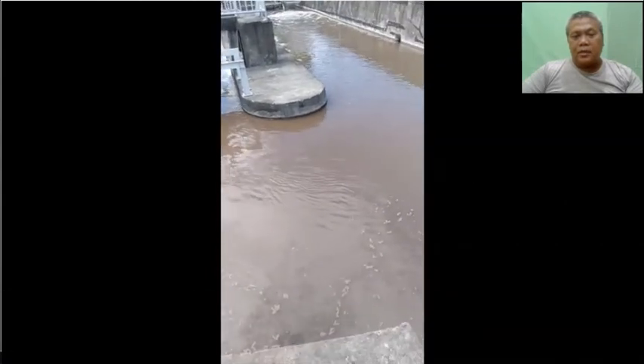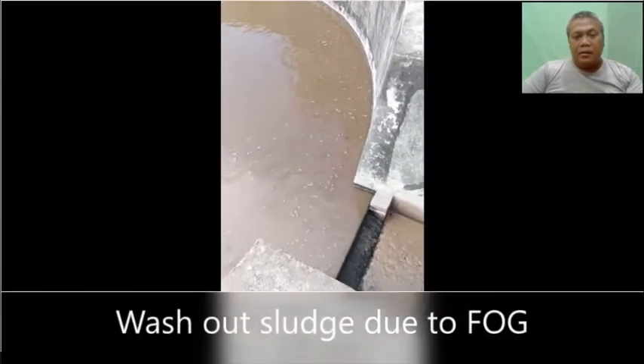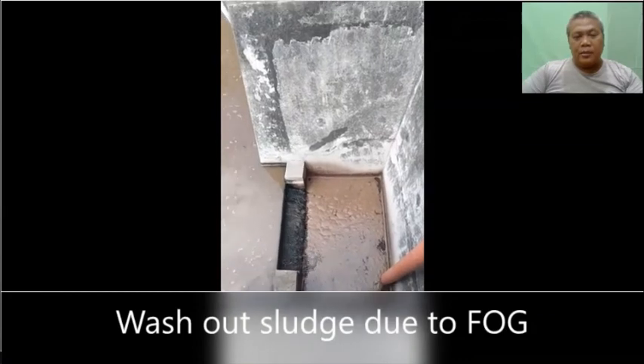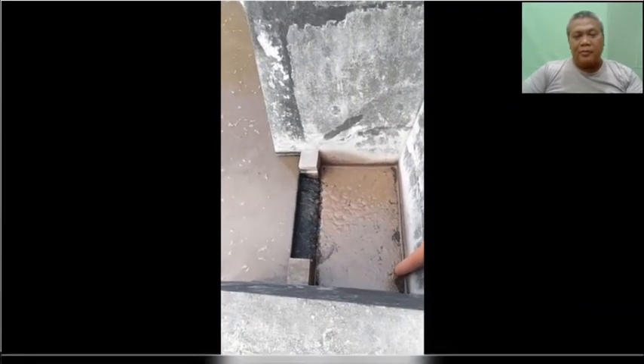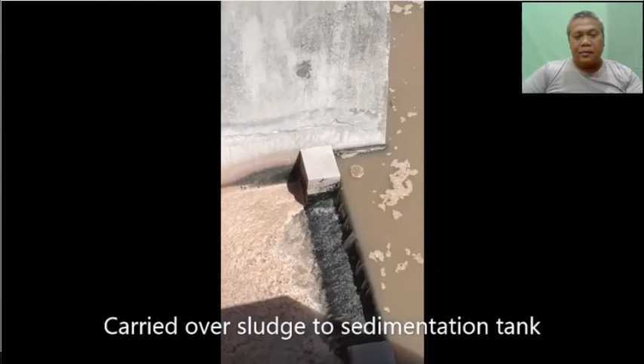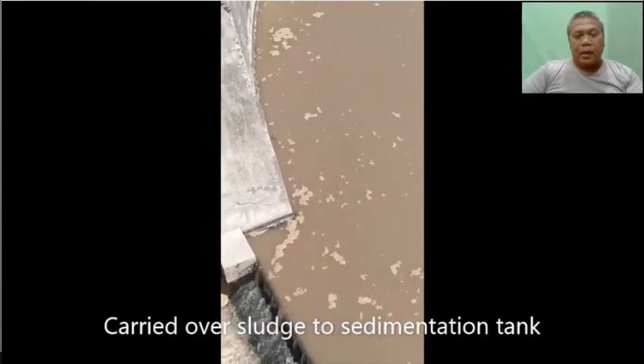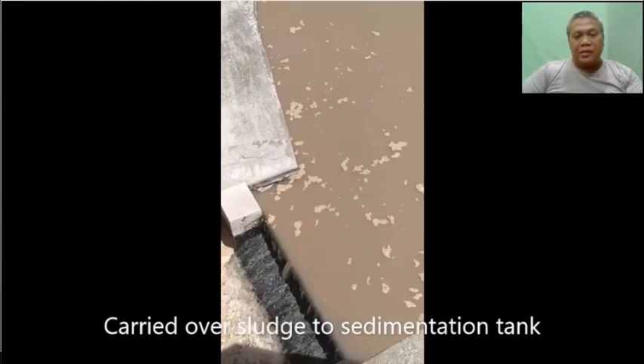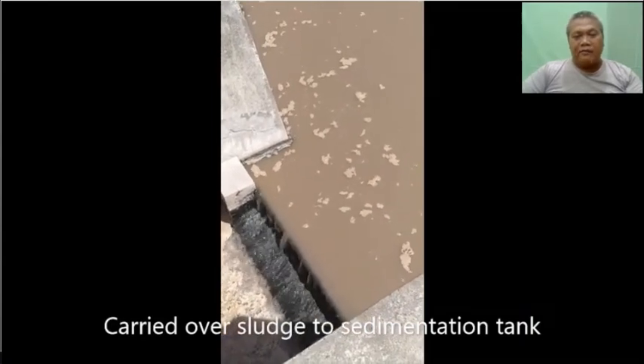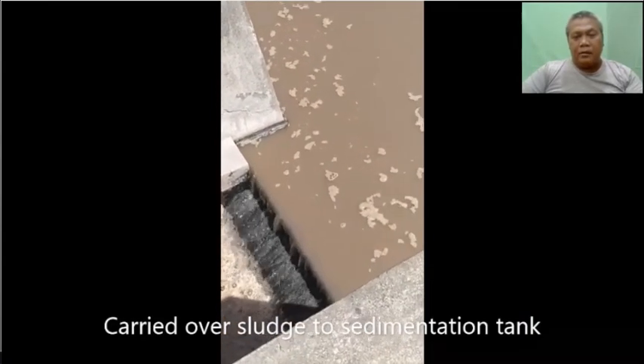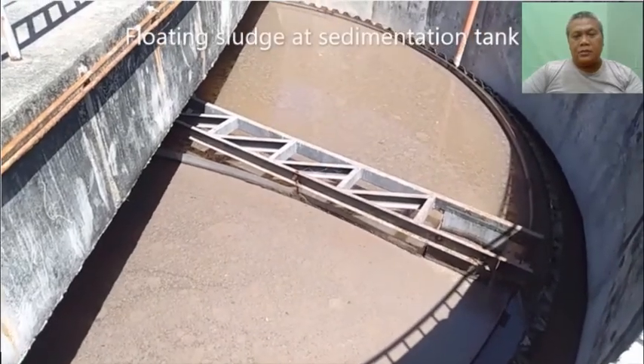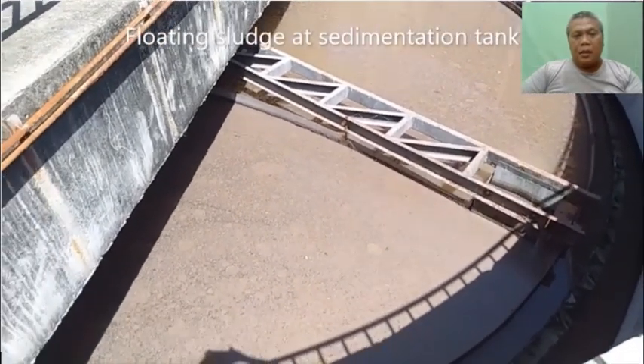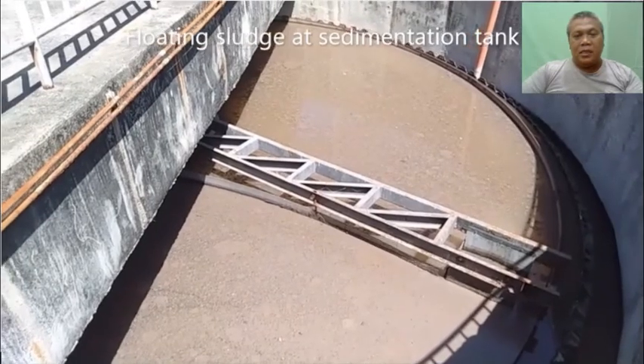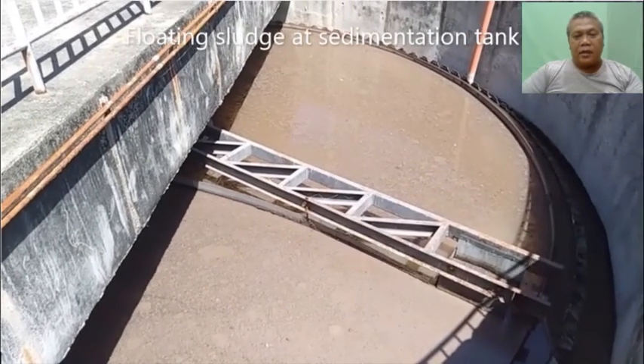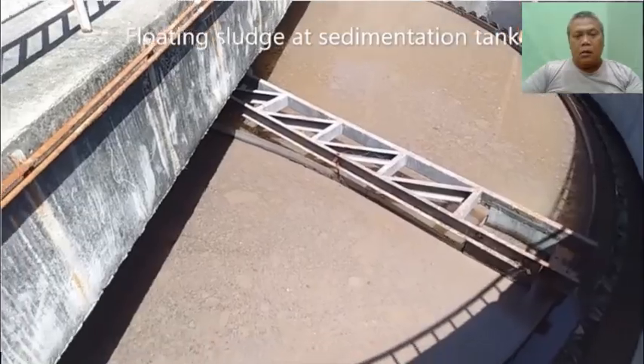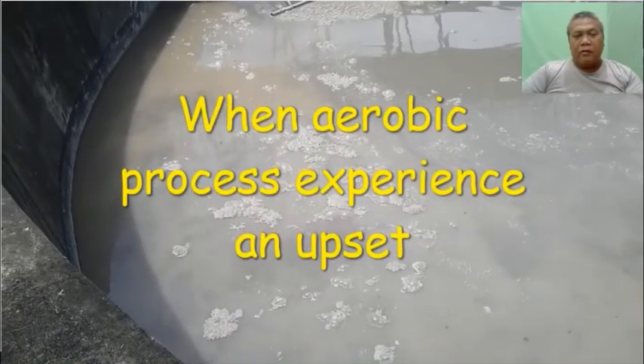We encountered lots of problems like floating sludge, especially when fat, oil, and grease is coming in. So this is what it looks like. And then it will be carried over to the sedimentation tank or clarifier. So in effect, we have less sludge retention. And here, as it reaches the sedimentation tank or clarifier, it floats on top of it, so it will be carried over.